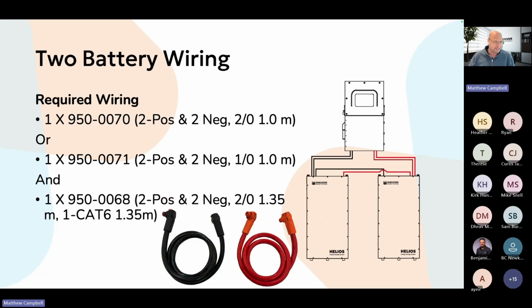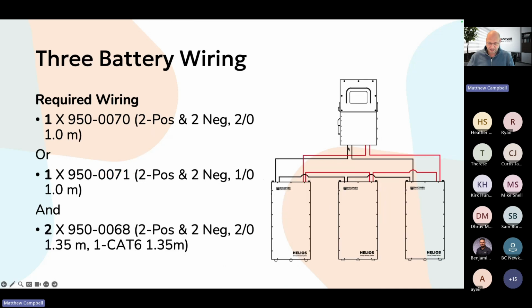If you're going to do 2 batteries, you'll need what we just talked about on the other page, so either one set of 1-aught or 2-aught, plus our parallel kit. The parallel kit comes with 2 positives and 2 negatives, and you can see how they'd be wired together, or recommended to be wired together. It also comes with a Cat6 cable for communications between the batteries. Each battery in the box comes with a Cat6 cable for going from the battery to the inverter, but the kit includes an extra, slightly longer cable for going between the batteries.